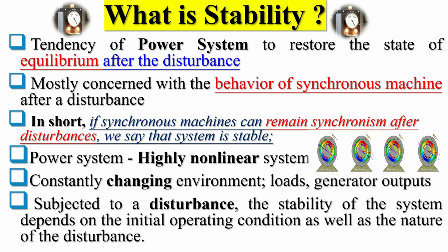Stability is the tendency of a power system to restore the state of equilibrium after a disturbance. It is mostly concerned with the behavior of synchronous machines after a disturbance. In short, if synchronous machines can remain in synchronism after disturbances, we say that the system is in a stable position. A power system is a highly nonlinear system, in a constantly changing environment, with loads and generator outputs varying. Subjected to a disturbance, the stability of the system depends on the initial operating condition as well as the nature of the disturbance.